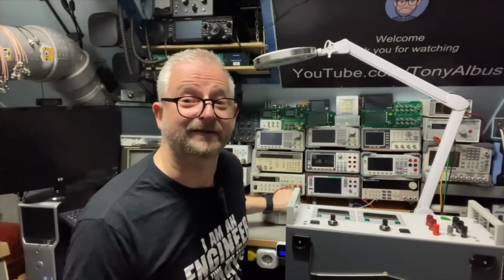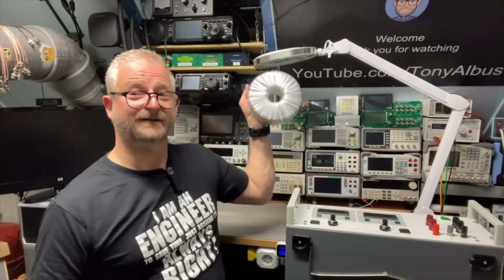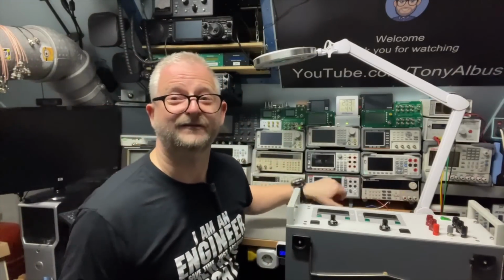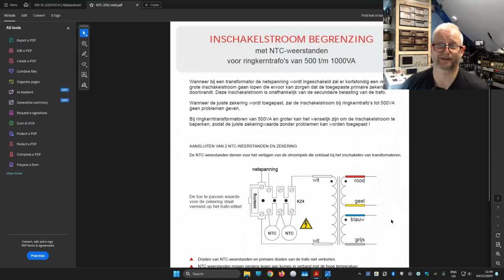That's the solution the seller and producer of these toroid transformers gave me. They sent me this document, it's in Dutch, and they say you need to put 2 NTCs in series, don't cut the winding shorter, just add them in series. It's for between 500 and 1000, and I think both are 5, so a total of 10 ohms, giving you a minimum resistance of 10 ohms.